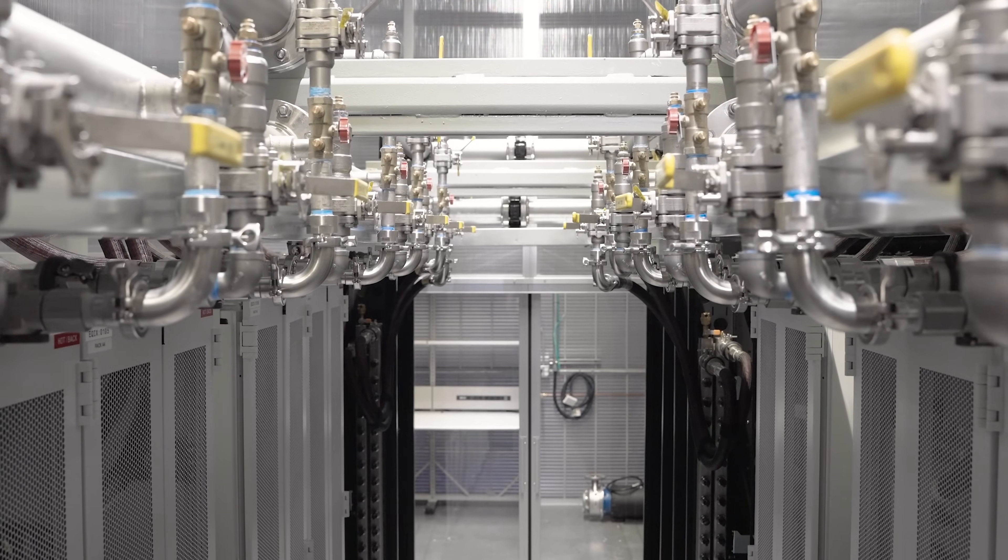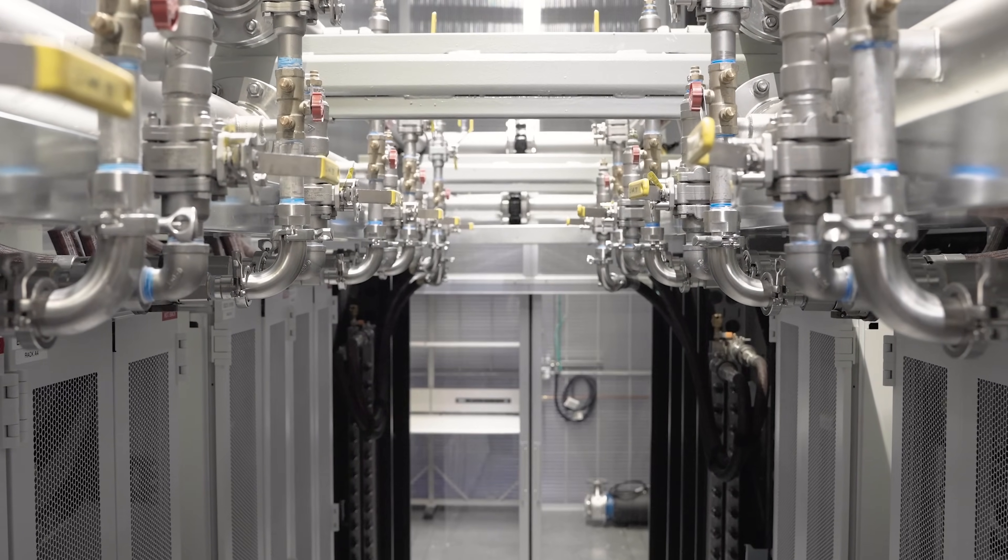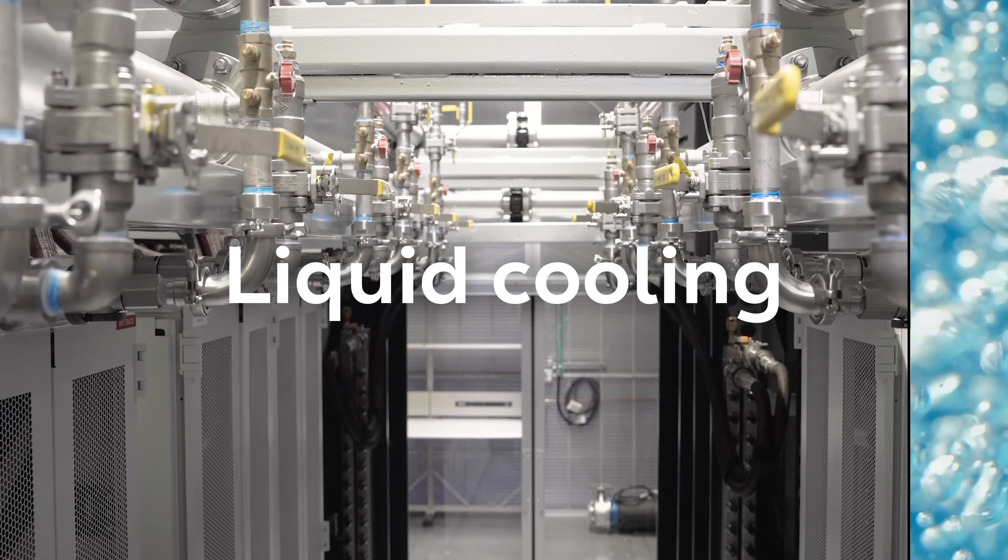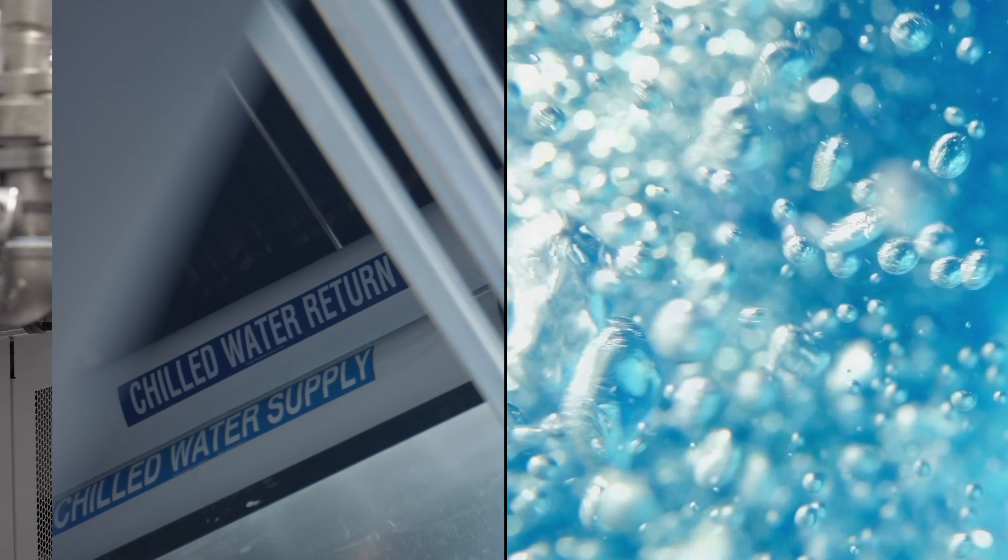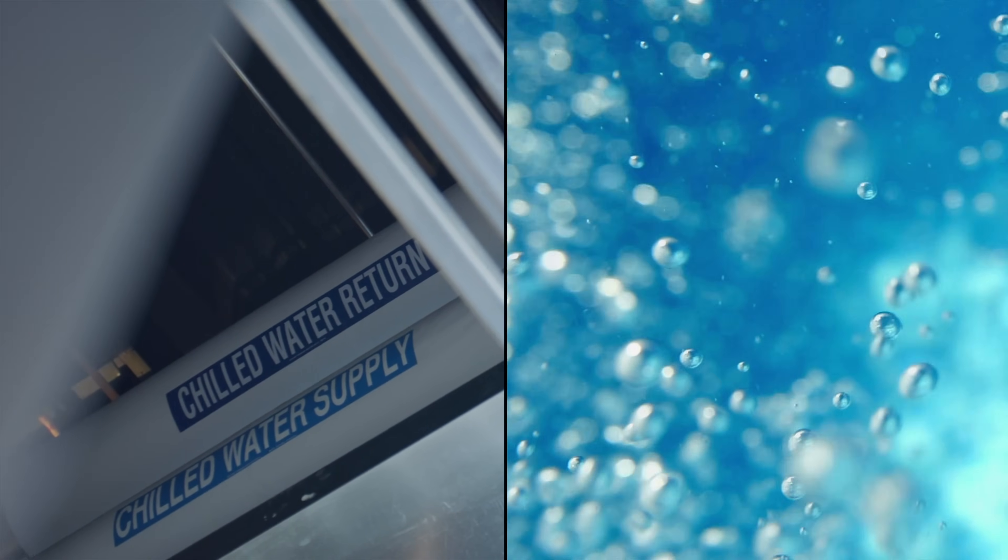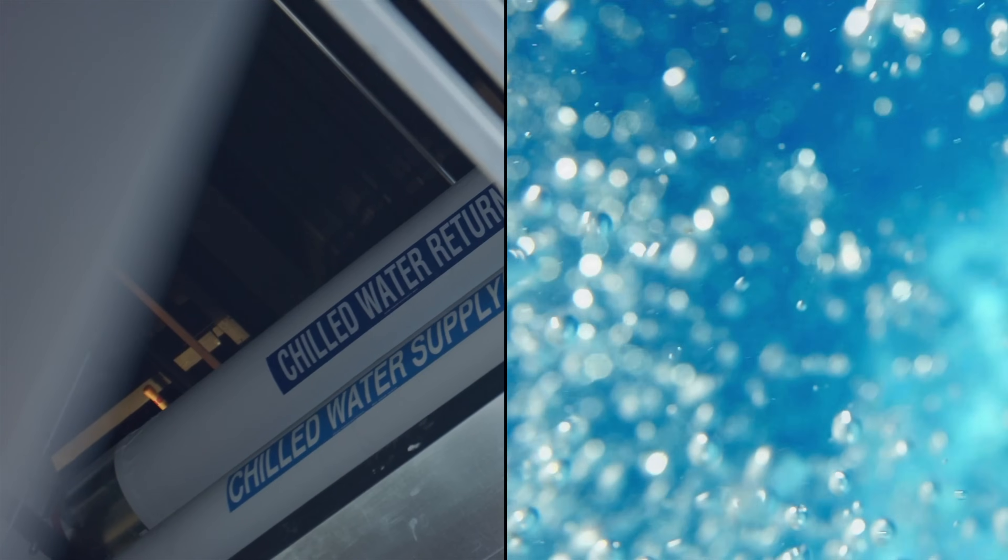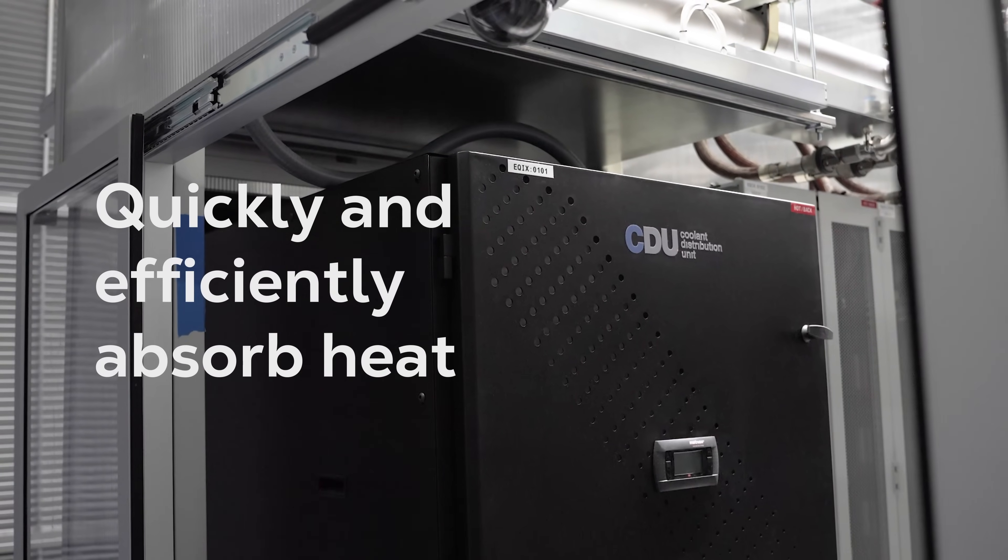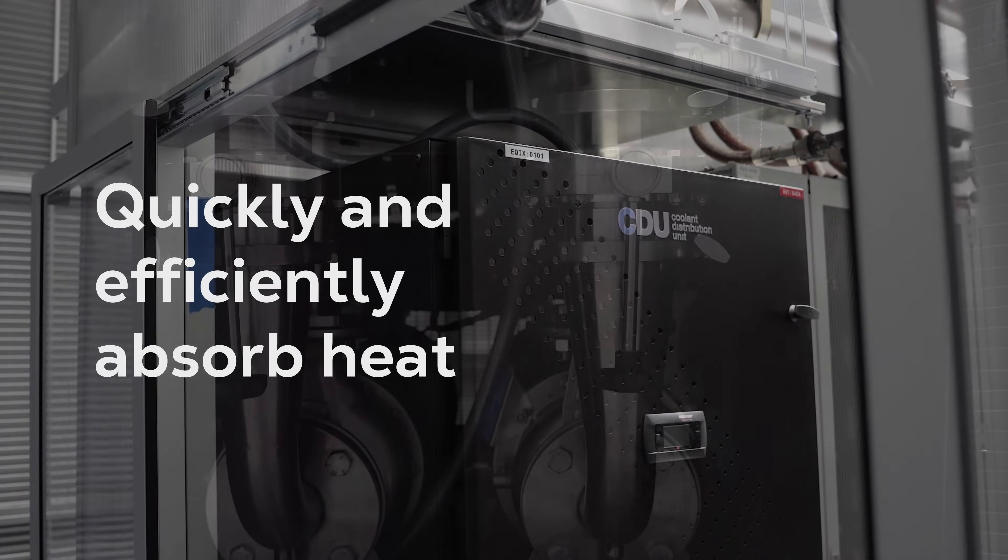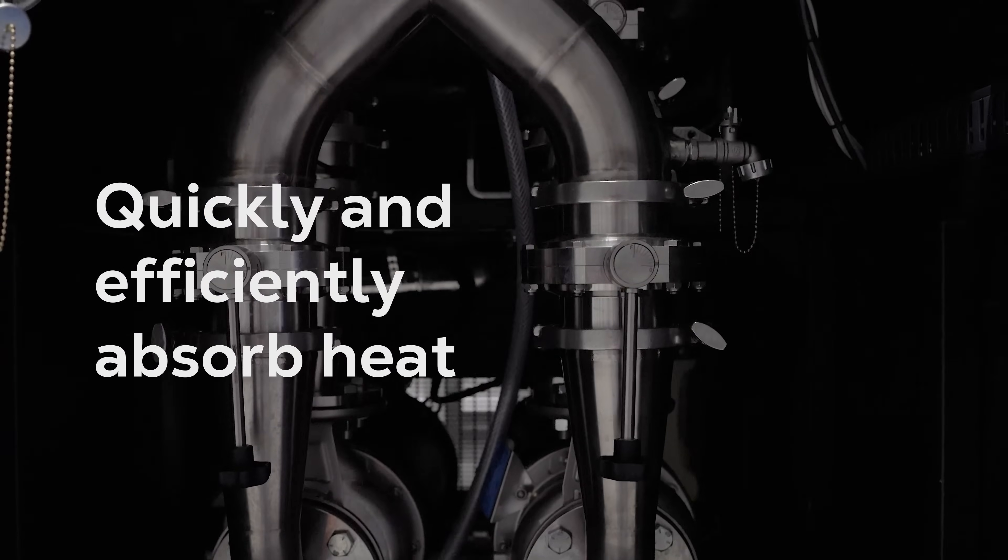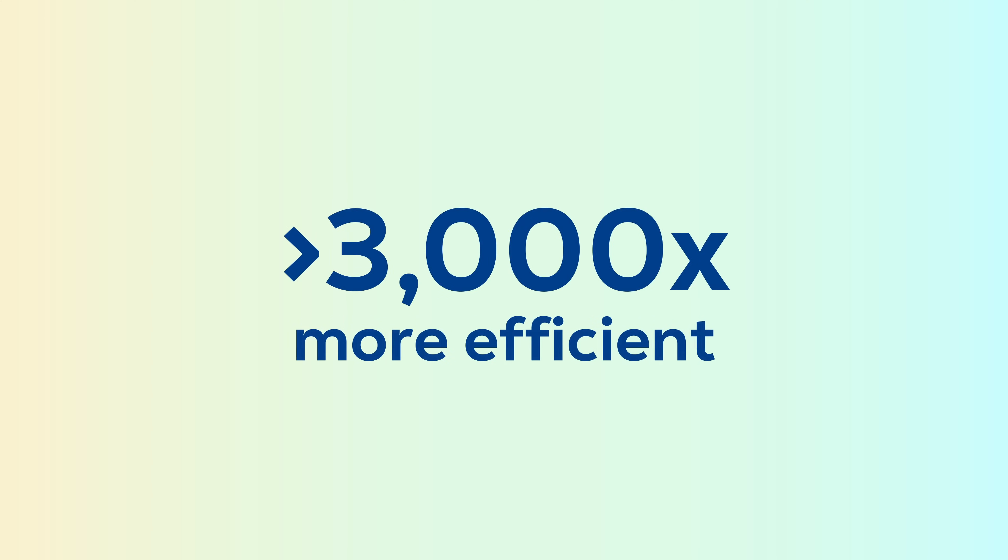A super-efficient way to regulate hardware temperature is with liquid cooling. This method uses pipes to circulate liquid, typically either water or a specialized coolant, to quickly and efficiently absorb heat directly from the equipment. Liquid cooling is effective because liquid conducts more than 3,000 times as much heat as air, and requires less energy to do so.